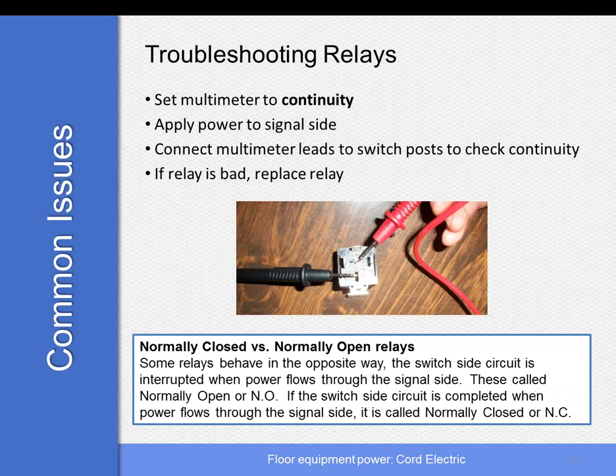We'll test just like switches. We'll set to continuity. And here we will have to apply power to the signal side or the coil side. And once we do that, the switch will engage and we'll get our normal. If it's on, we'll get the beep. If it's off, we'll get silence.